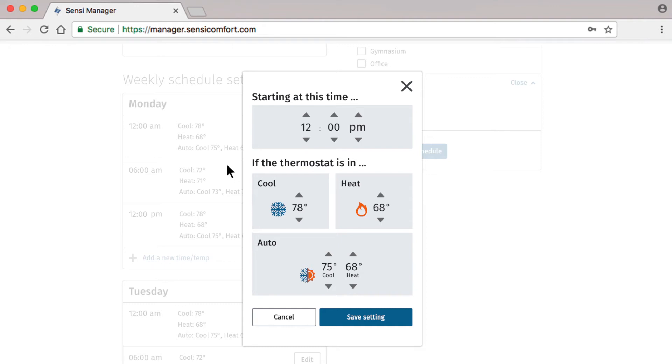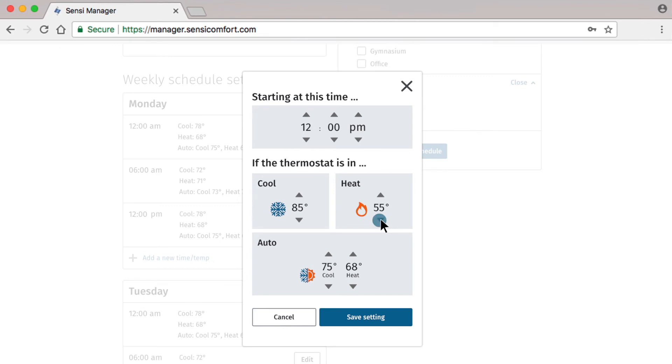Since this is a vacation schedule, let's change the settings to conserve energy while keeping our building warm enough to prevent things like frozen pipes and cool enough to reduce humidity. In Cool Mode, let's set a maximum high temperature of 85 degrees. In Heat Mode, a maximum low temperature of 55 degrees. And in Auto Mode, we'll use the same set points to create a range. Then we'll save the settings.